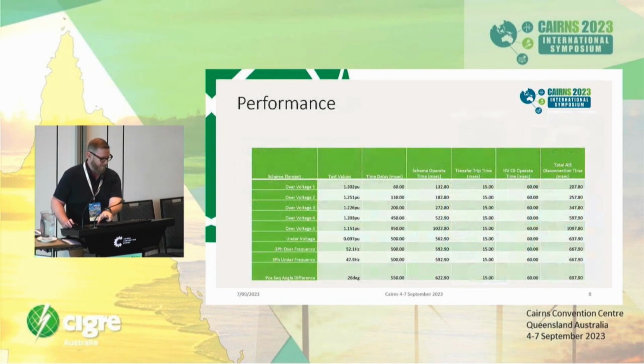So moving on, just to give you an idea of what it all looks like in the end. So these are some of the performance results. So for our fastest overvoltage element, it's understanding what the inherent delay is and using synchrophasors as well. So if our synchrophasor delay is 60 milliseconds for the overvoltage element, the actual operating time is about 70 milliseconds slower. So you take into account your comms latency and so on.